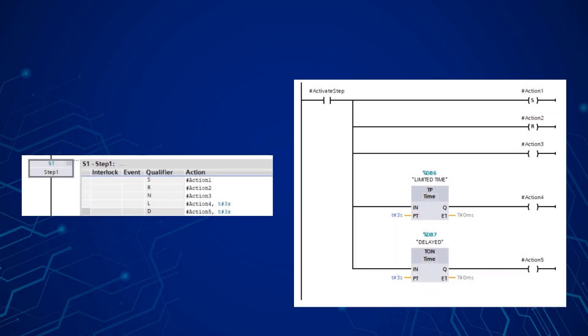In these pictures I tried to represent the basic actions a step offers. The set commands are in the first line, the reset in the second, and the N command equals a binary output. The limited time can be programmed using a pulse timer and a binary output. The delayed time can be programmed using an on-delay timer and a binary output. We can't use a set because in the graph, when you exit the step, the delayed tags lose their true status.